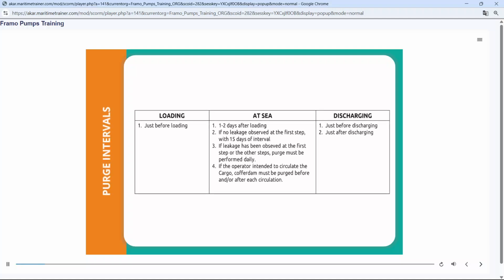Purge intervals. Loading: just before loading. At sea: 1-2 days after loading. If no leakage is observed at the first step, purge at 15-day intervals. If leakage has been observed at the first step or the other steps, purge must be performed daily. If the operator intends to circulate the cargo, the cofferdam must be purged before and/or after each circulation. Discharging: just before discharging and just after discharging.